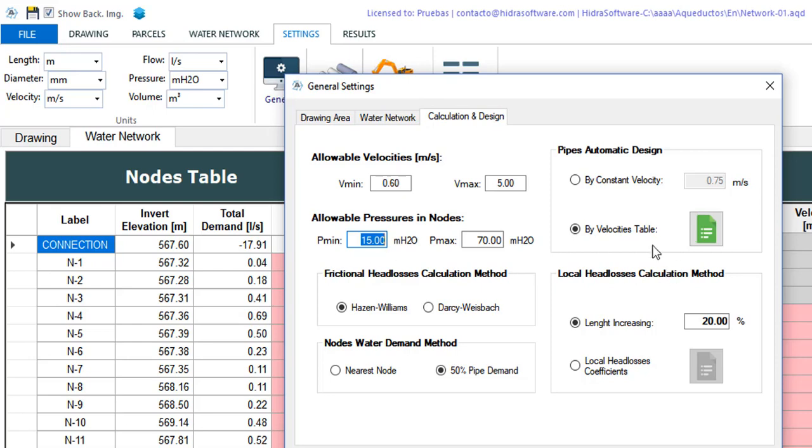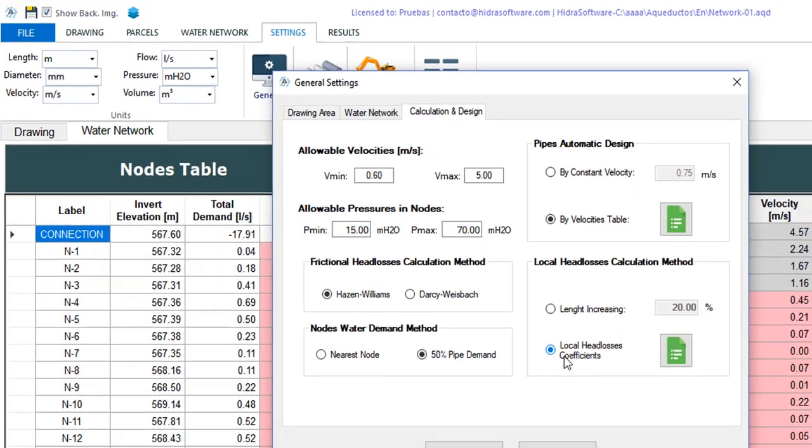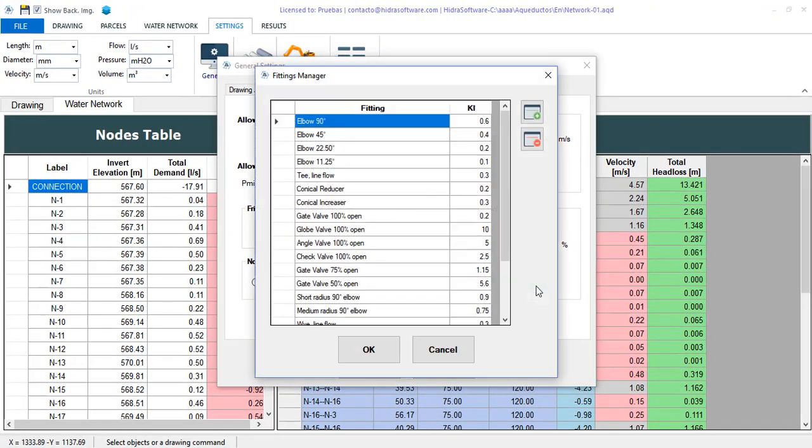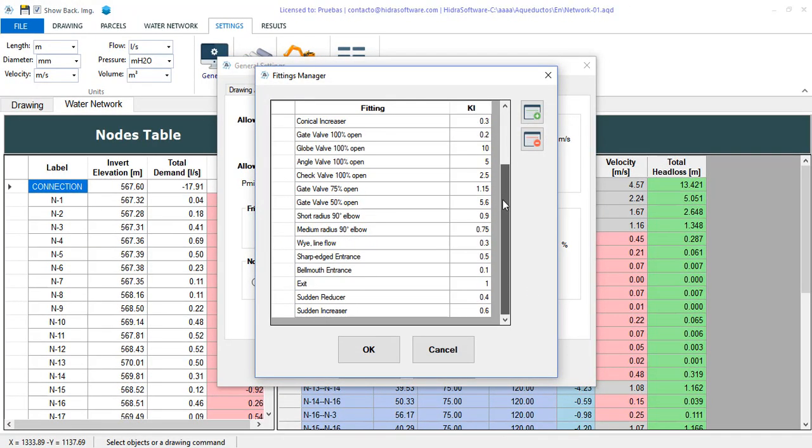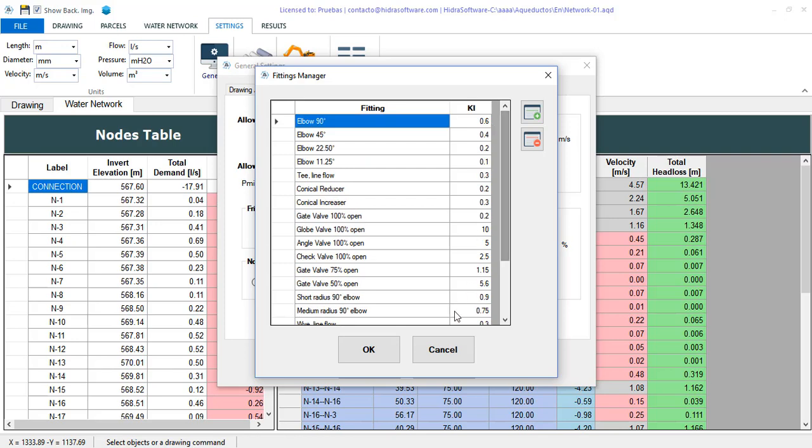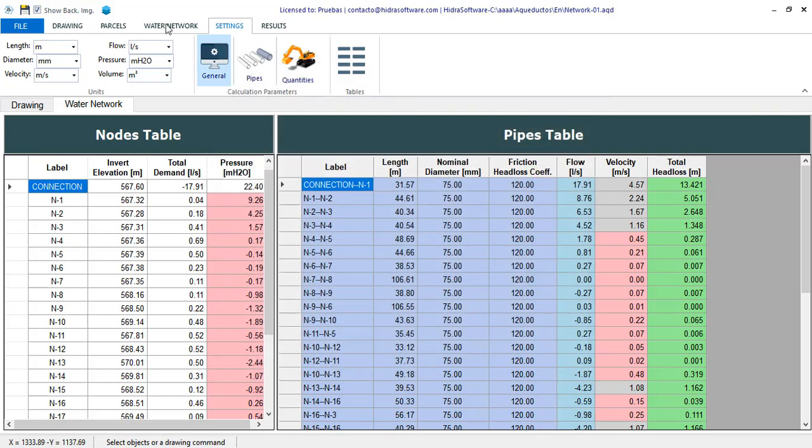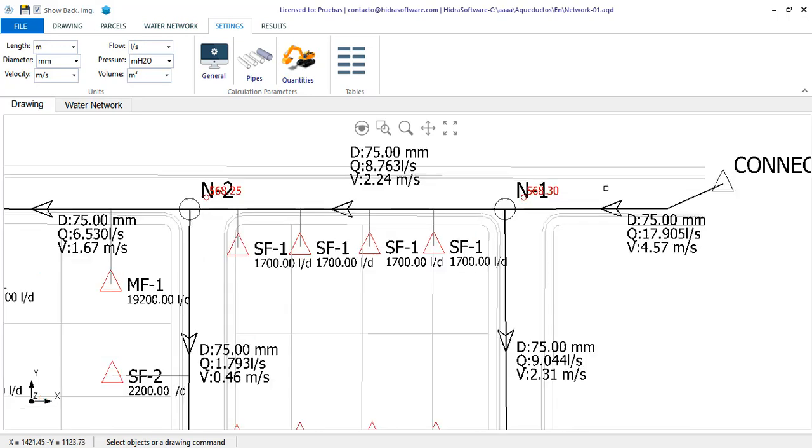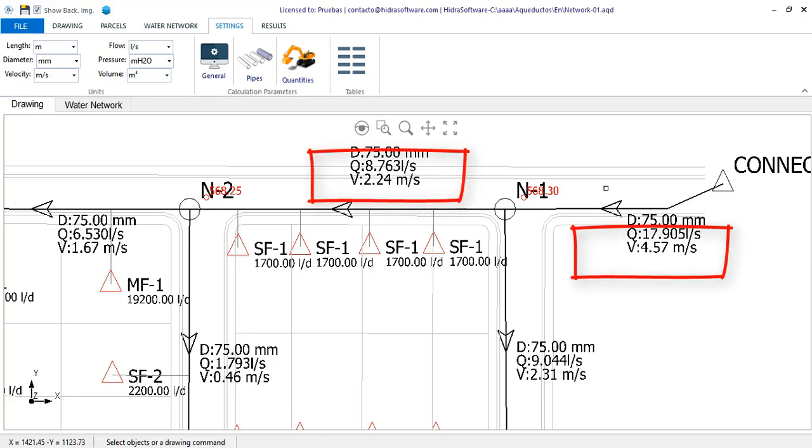Here, to show you another of the characteristics of the software later, I will change the local head losses calculation method to coefficients, in which case the values we have defined in this table are used. Returning to what concerns us, the design of the water network, it is clearly necessary that the diameters be modified to not only reduce the high velocities that we have in pipes like these, but also to improve pressures in nodes by reducing head losses.